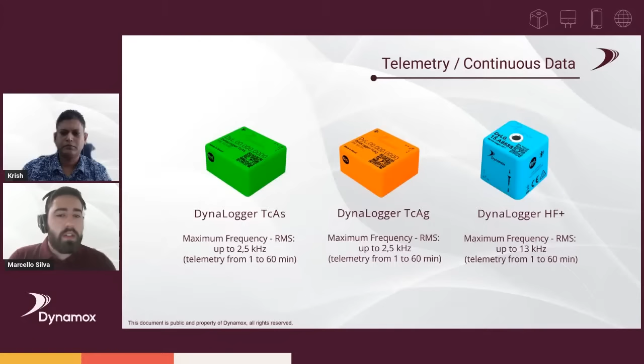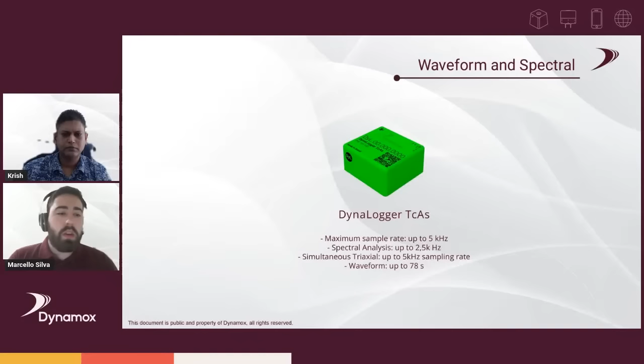Okay. Spectral. Our TcAs, this green one, can go up to 5 kilohertz of sampling rate, which would guarantee us a 2.5 kilohertz spectral analysis, or Fmax, as you prefer. In terms of simultaneous triaxial, up to 5 kilohertz sampling rate as well, and the waveform can go up to 78 seconds. So this can cover, for example, conveyor pulleys that usually have bearings where the speed is not that high. So this would cover this kind of case with good consistency.